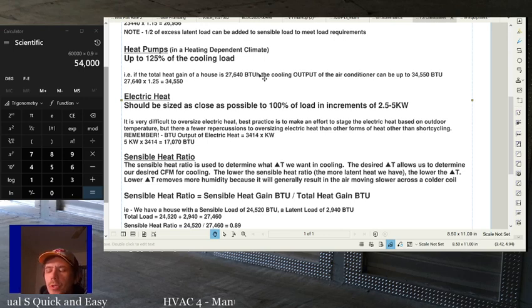So when we're talking about oversizing air conditioners, what's the problem with oversizing them too much? Well, the problem with oversizing them too much is you can end up with high humidity in the home because the equipment's short cycling. So if you start going way too much over the load requirement of the equipment, your equipment's going to short cycle more, especially on mild days, and you're not going to be able to maintain lower humidity levels. Of course, we're assuming single stage standard equipment here, right? We're not talking about variable speed equipment that can control the humidity in the house using sequences where it lowers the fan speed at the beginning of operation and so on and so forth. If you're putting in single stage standard equipment, 14, 16 SEER or something like that, then if you oversize it, you could end up with high humidity in the house, again, especially on mild, humid days. So we don't want to oversize it too much.